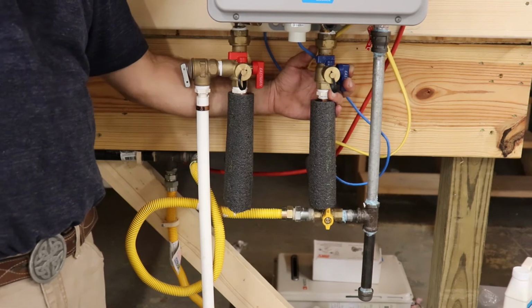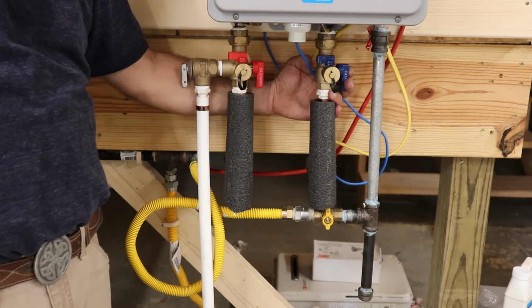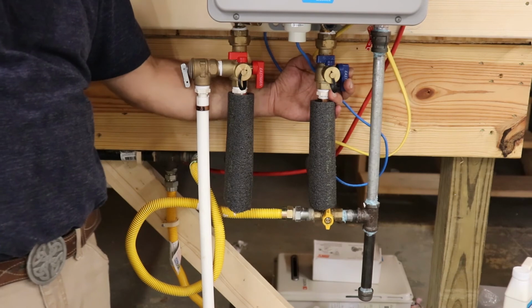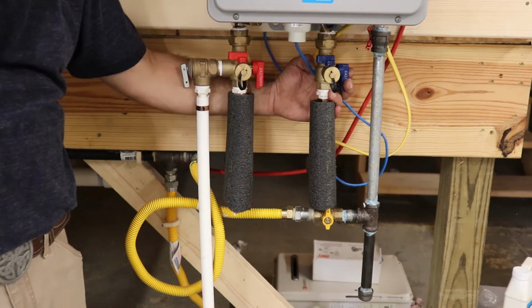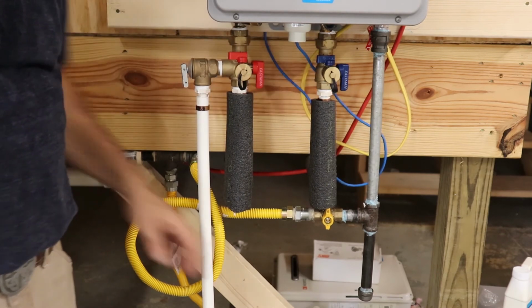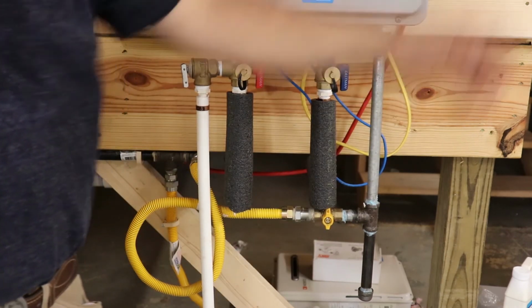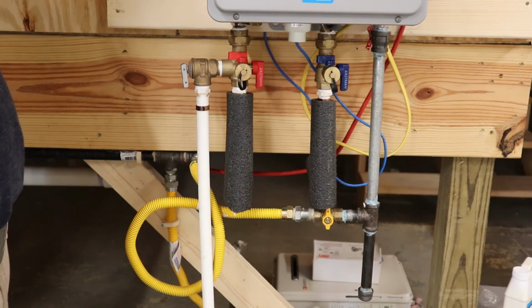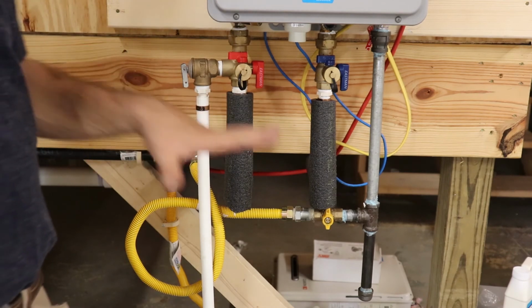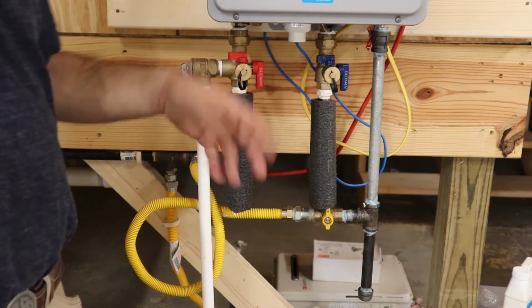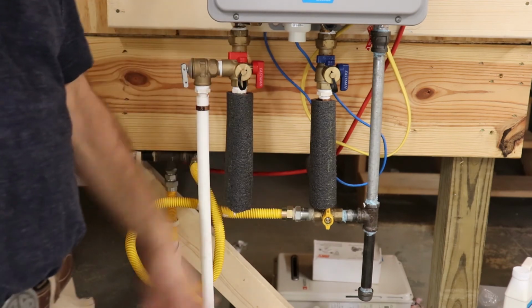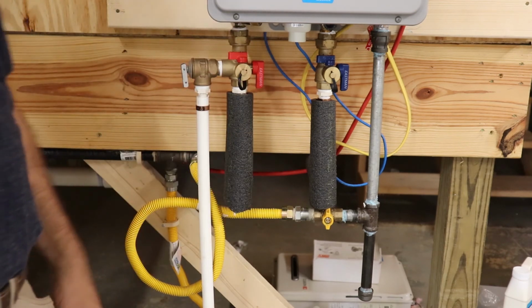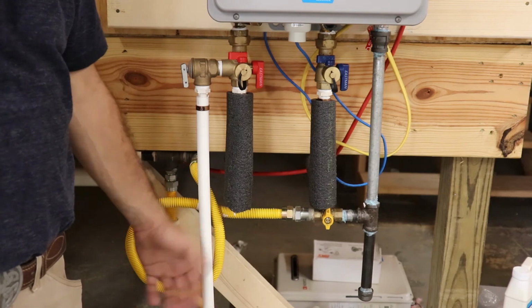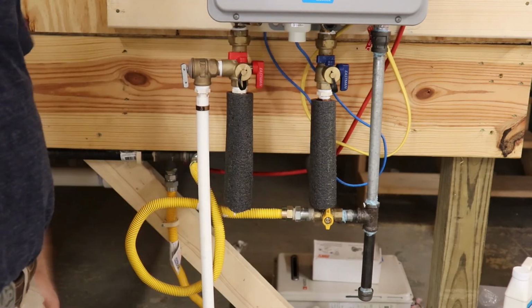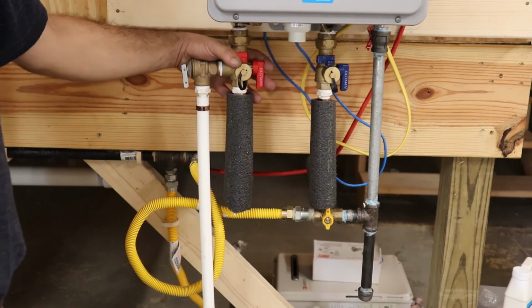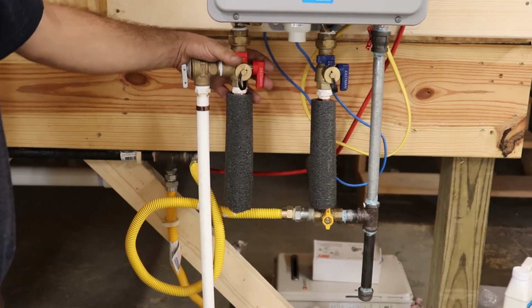Because the worst thing in the world is when you get about 10 miles down the road and your phone rings and it's that homeowner saying, I don't have any hot water. And it's because you did something stupid, like you left your valves off, you didn't turn your gas on, you didn't turn the power on your heater, or you didn't turn the power on that controller. Make sure everything works before you leave. Don't get all excited and get on down the road and then have to go back. Or at worst, you get a call at 9 o'clock at night, you ain't got no hot water, and you got to drive 20, 30 miles to this house and find out you left a valve off.